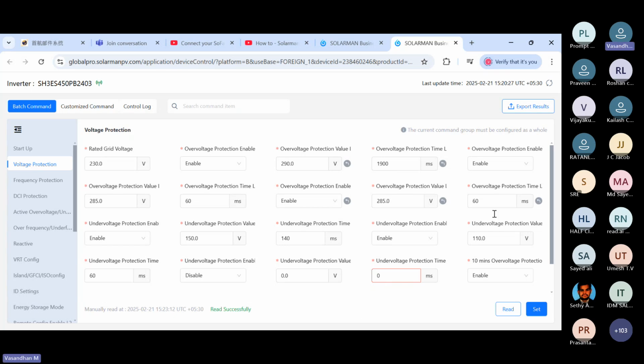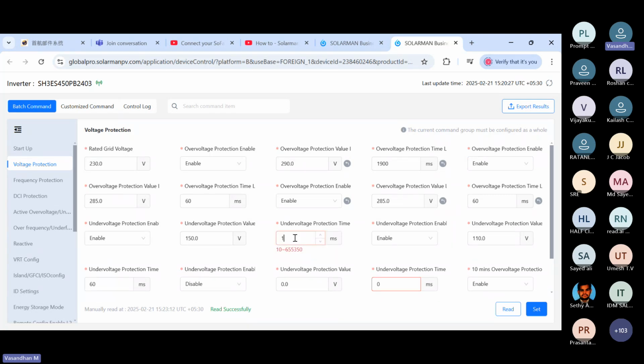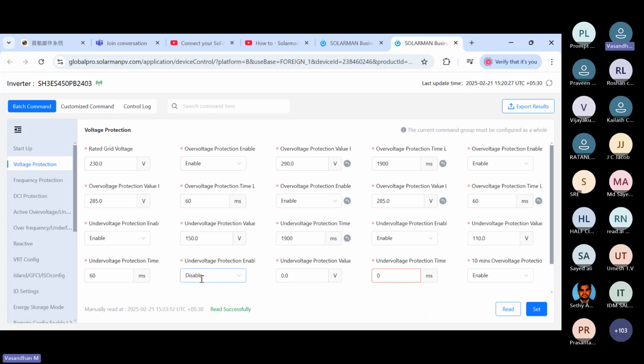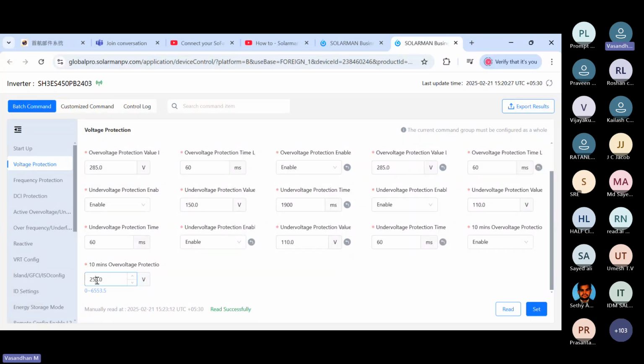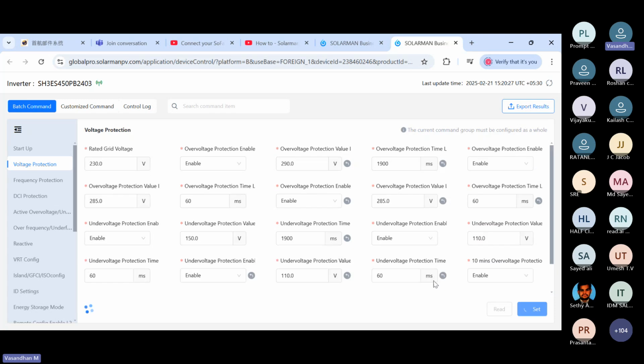This is nominal. And these are under voltage, over voltage. The top ones are over voltage; below, we can set lower voltage values. It is 110, 60, this is enabled. There are 3 levels, over voltage and under voltage, 3 levels each. Maximum 290, minimum 110, we can set. And the 10 minute over voltage value is 285, 285 like this. So I already set it.